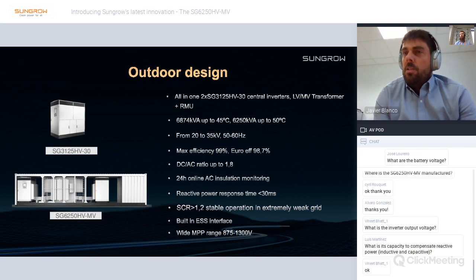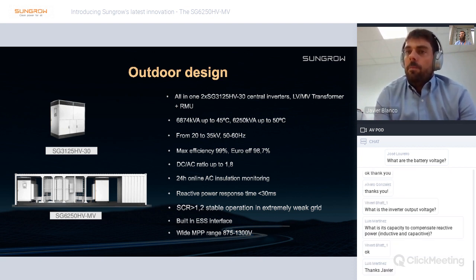So what is the capacity to compensate reactive power, in inductive and capacitive? Like I mentioned, it's power factor plus and minus 0.8 at rated power, at 6.87 MVA. That is the reactive power capability.